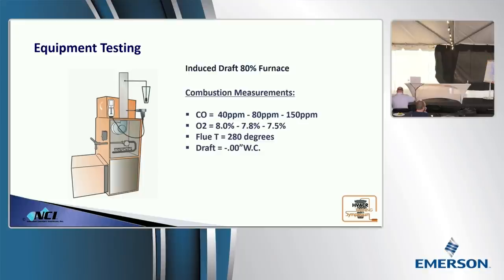For those of you that haven't, what's wrong with that? Why is that a problem? We're depleting oxygen. If an analyzer could talk, somebody will invent this soon, if you see rising CO and falling oxygen, it's going to tell you that flue gases are backing up in the equipment and I'm running out of combustion air. That's what those readings are telling you. The flue gases are backing up in the heat exchanger. I'm running out of combustion air. Oxygen is not making it into the burner. And just imagine it talking like me. You'll never forget it. So with these readings, we have a combustion air problem. These are classic combustion air symptoms.